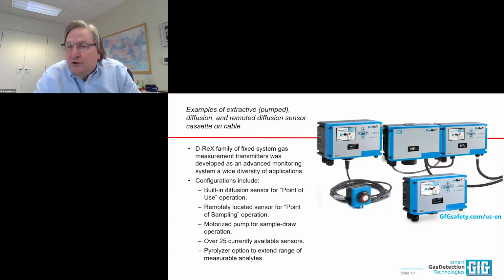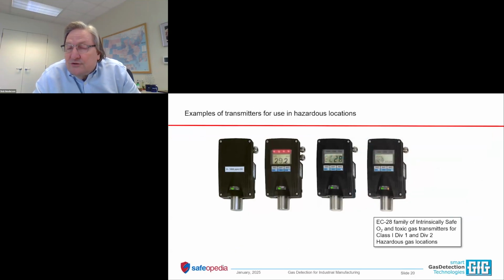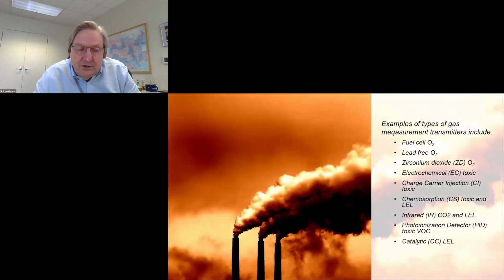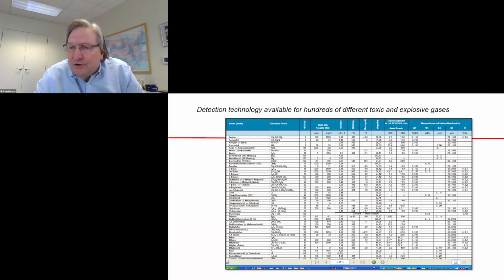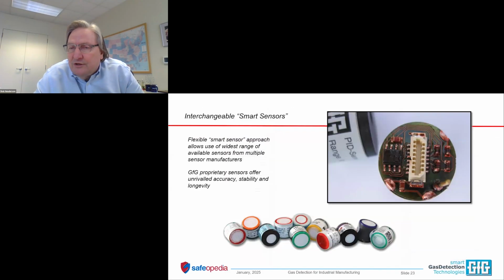As it turns out, these are all designed for use in non-hazardous locations. If we want to measure the same molecules in hazardous locations, we can go back to the explosion-proof protective concept or transmitters that are based on the intrinsic safety protective concept. The kinds of technology that we have available for fixed gas detection, we've got a lot more options than we have with portables. So it really is very important for the manufacturer to understand fully what you need to accomplish, because we have so many ways that we can configure the system.